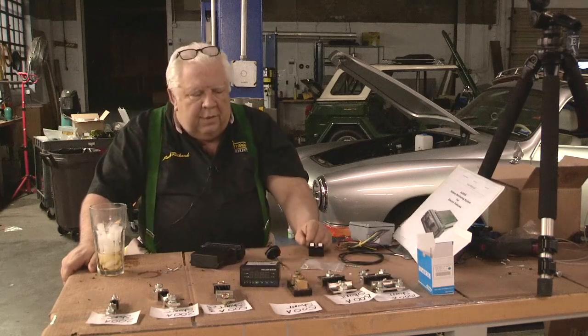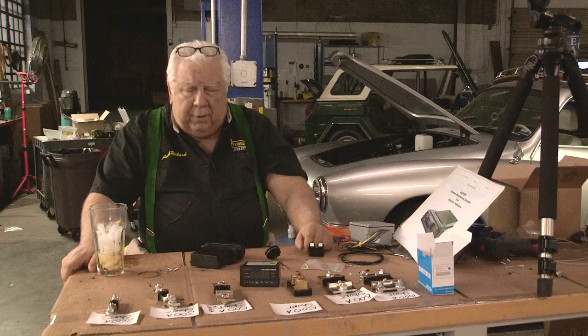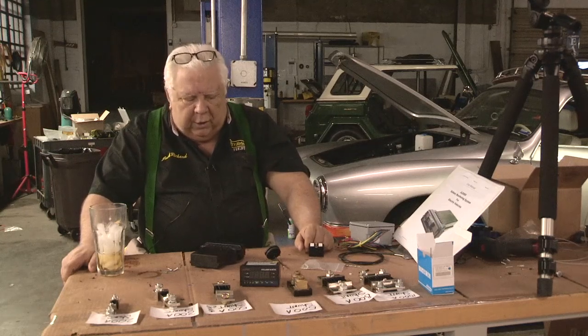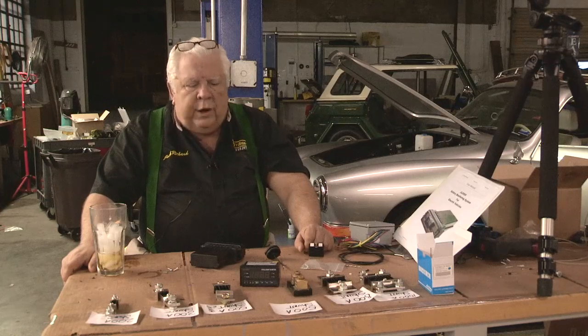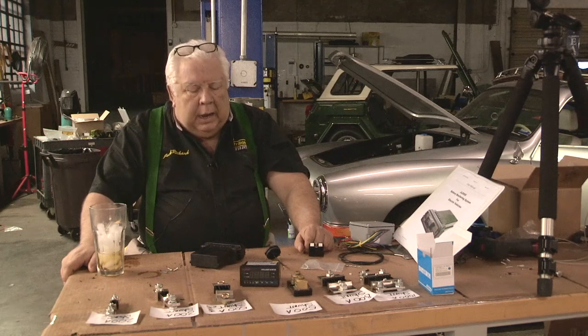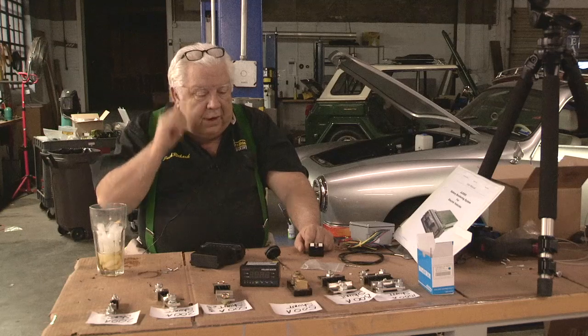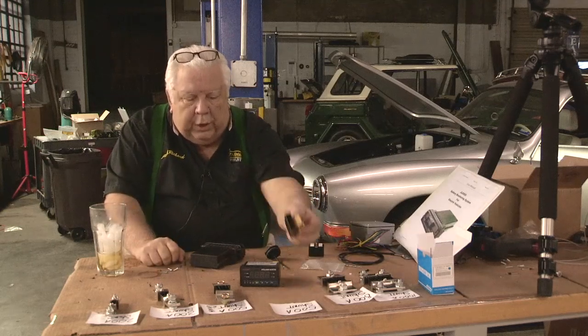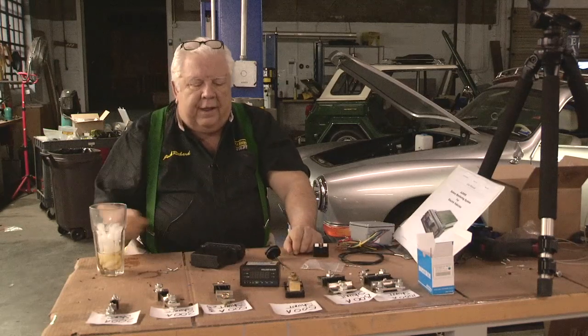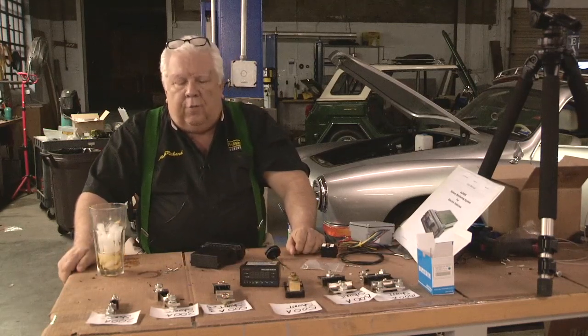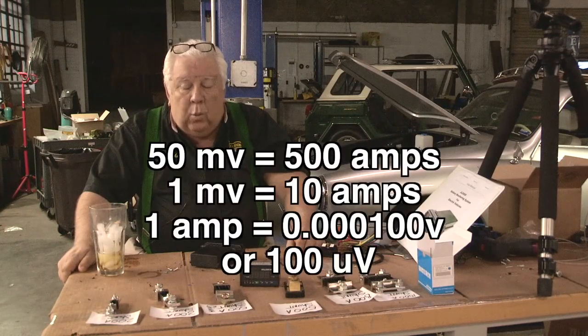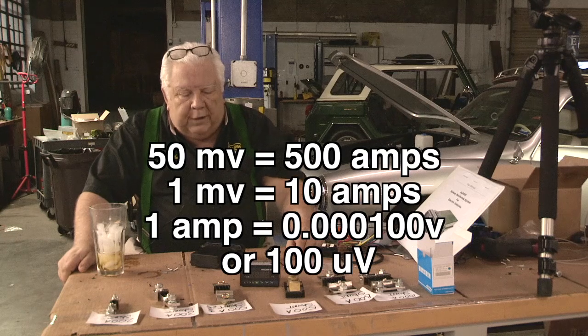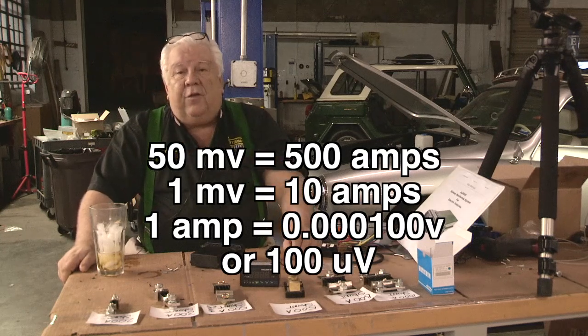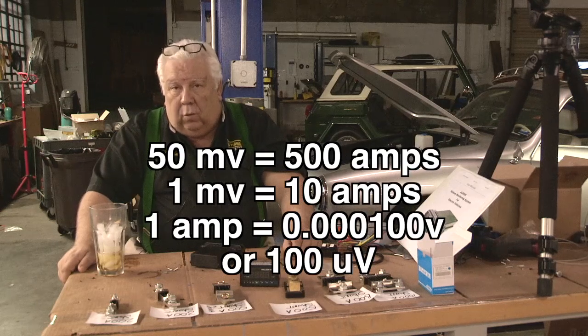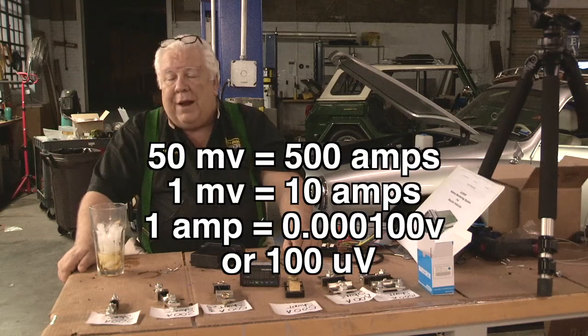The 750 amp, 75 millivolt might be built a little heavier to carry more current longer. We're never in a situation where we need to carry these high currents for any length of time at all. Now again, if this is 50 millivolts and we're reading 500 amps, that is about 10 amps per millivolt. And so we have to be able to detect a 1 millivolt, 1/1000th of a volt change to discern 10 amps. And so 1 amp would be 1/10 of a millivolt, or about 100 microvolts.